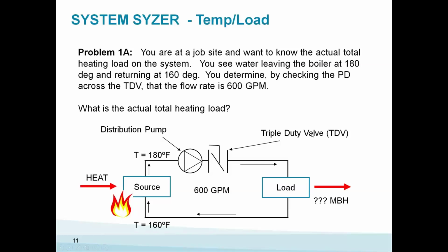One last thing that sometimes the guys out in the field, whether it be us, our salesmen out in the field to help troubleshoot or problem solve, sometimes contractors or whoever it is, but here we're out in the field and we get some real world conditions. And we're saying, hey, I've got a boiler plant. I've got a leaving water temperature I can see on the gauge of 180 degrees, and it's coming back at 160.